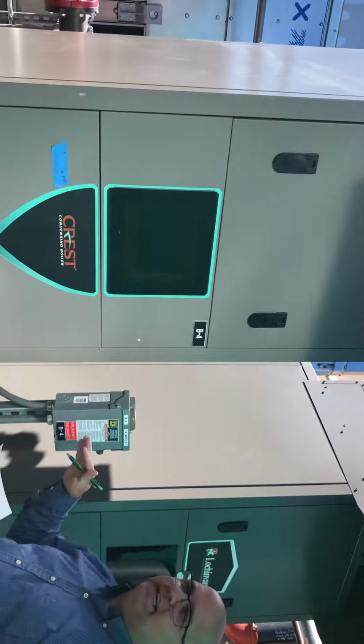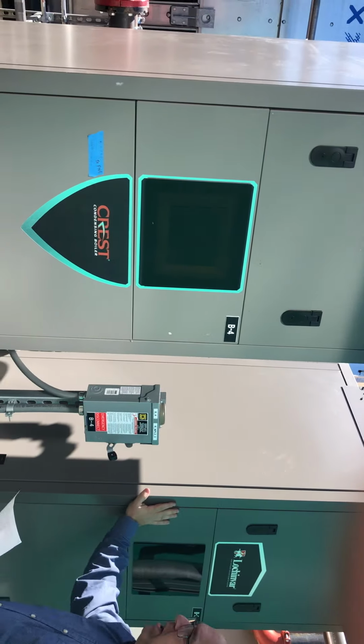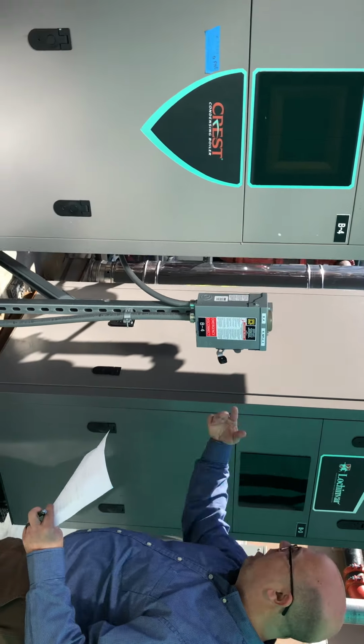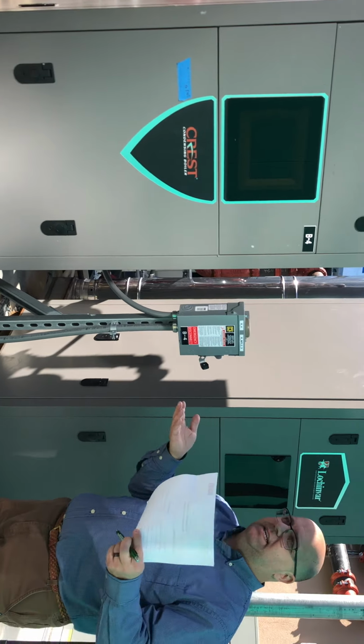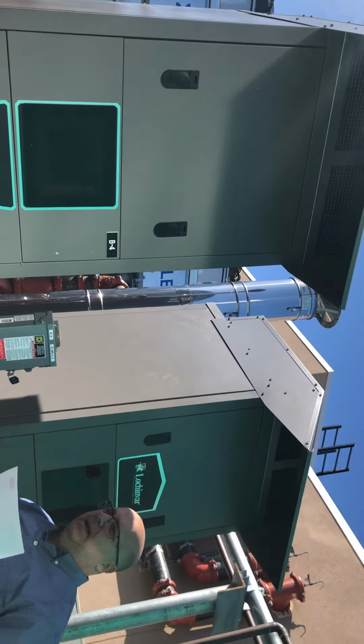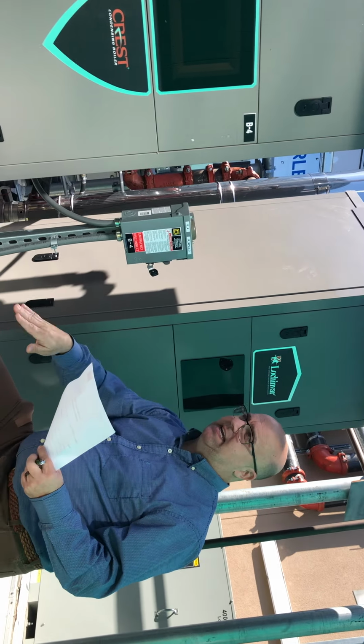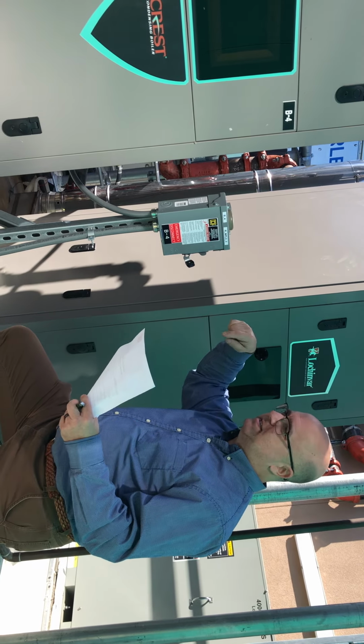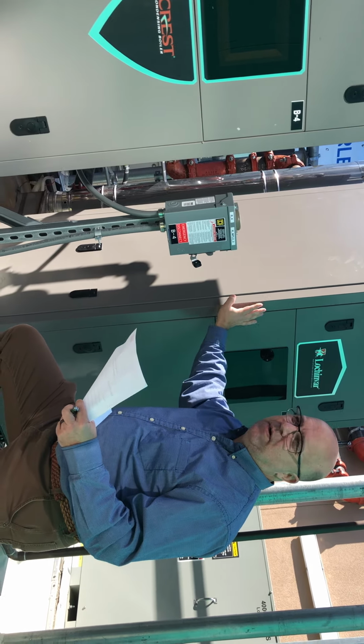Unfortunately, boiler 4 right now is inoperable, it's under some repair, but boiler 3 is still doing its job. And it's taking the water that's coming back from the rooms and making sure that it doesn't drop too cold. Now, as it turns out, I don't actually want to turn this boiler on until it gets below 60, but the boiler itself right now has a low limit of 70. Okay. So it's kind of idling itself along at 70 degrees.